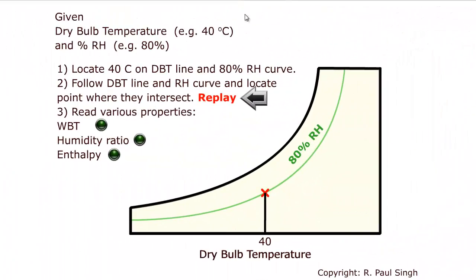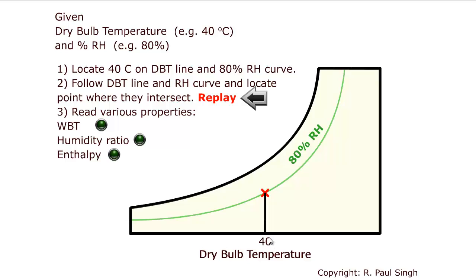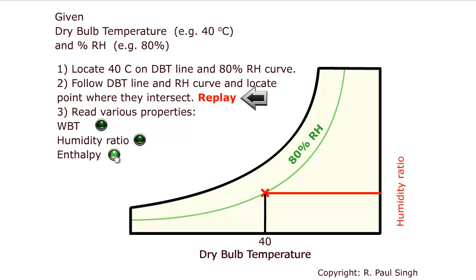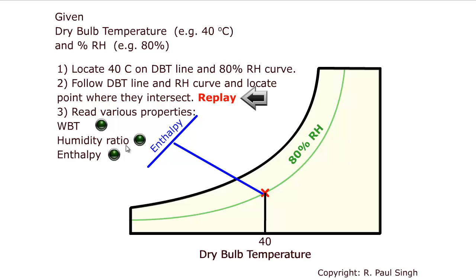Let's look at another example where the dry bulb temperature is 40 degrees C and relative humidity is 80 percent. On the chart we find where the 40 degrees C dry bulb temperature line meets the 80 percent relative humidity curve. From that point, we determine the wet bulb temperature by following the wet bulb line, the humidity ratio by following the horizontal line, and the enthalpy by following the constant enthalpy line — which is the same as the wet bulb line.